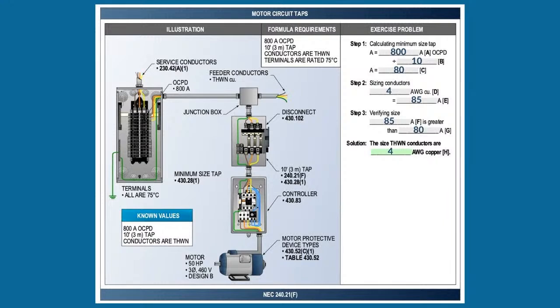Well, I just want to know where the feeder conductors are in that whole illustration, because the branch circuit conductors could carry through all that as long as you don't have fuses. Yeah, well, the feeder is because it's going through feeding two or more loads, like I was saying earlier. And then everything down from that point is a branch circuit. But in this case, you're sizing it as a tap. So you've got to know what is the minimum size those tap conductors can be, and then you're looking at the size overcurrent device minimum there. But you need to also do the calculation for that 50 horse. And I'll give you an example. I can tell you that's the minimum size that's required, but that size is going to be larger.